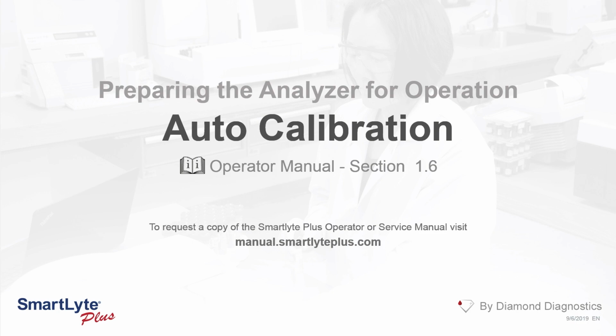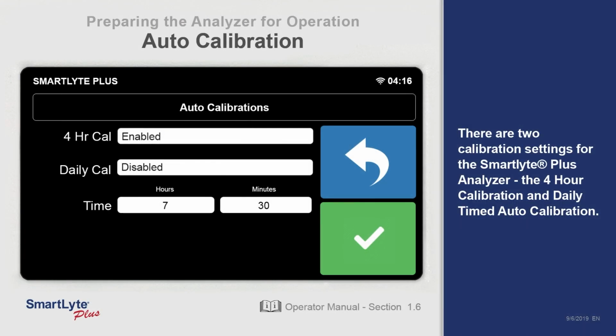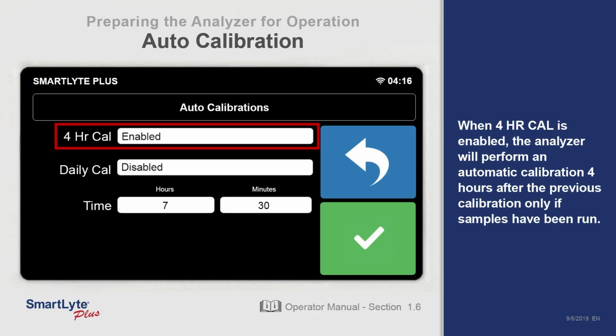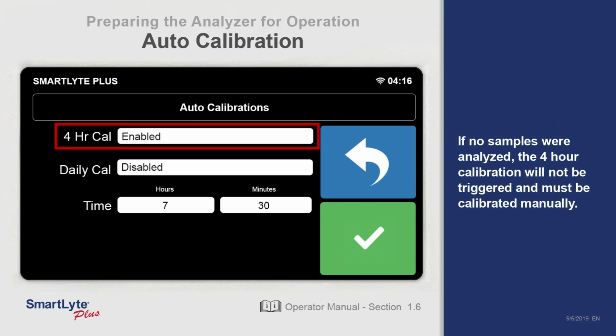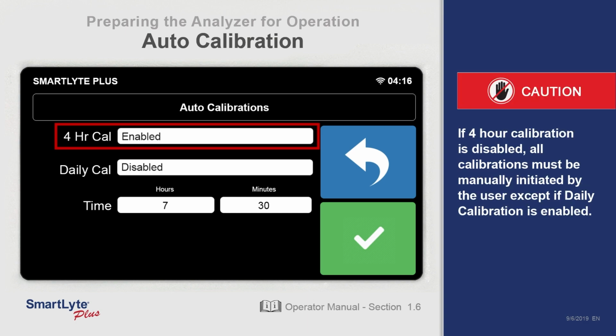Setting the auto calibration on the SmartLyte Plus. There are two calibration settings for the SmartLyte Plus analyzer: the 4-hour calibration and daily timed auto calibration. When 4-hour calibration is enabled, the analyzer will perform an automatic calibration 4 hours after the previous calibration, only if samples have been run. If no samples were analyzed, the 4-hour calibration will not be triggered. If 4-hour calibration is disabled, all calibrations must be manually initiated by the user except if daily calibration is enabled.